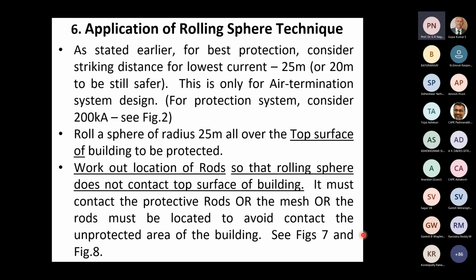Internal systems, I will not worry about in this set of webinars. So now I will repeat it. Work out the location of the rods so that the rolling sphere does not contact the top surface of the building. It must contact the protective rods or the mesh, or the rods must be located to avoid contact with the unprotected area of the building.